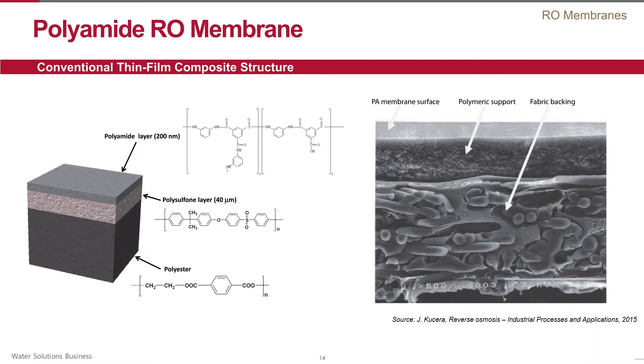One is a microporous polysulfone layer about 30 to 40 microns, cast on top of a reinforcing layer of polyester fabric that varies around 100 microns. The ultrathin polymeric film gives the RO membrane its salt rejection abilities and all other characteristics. The main functions of the two support layers are to reinforce the membrane structure and to maintain membrane integrity and durability.